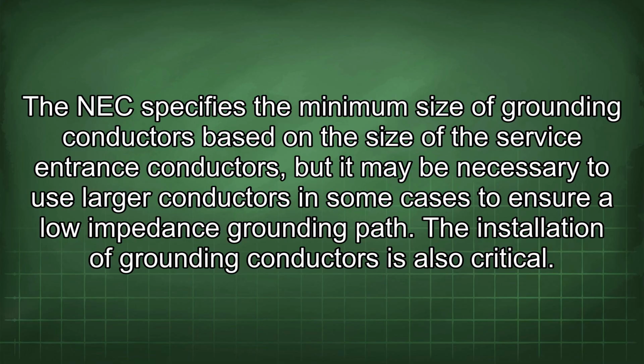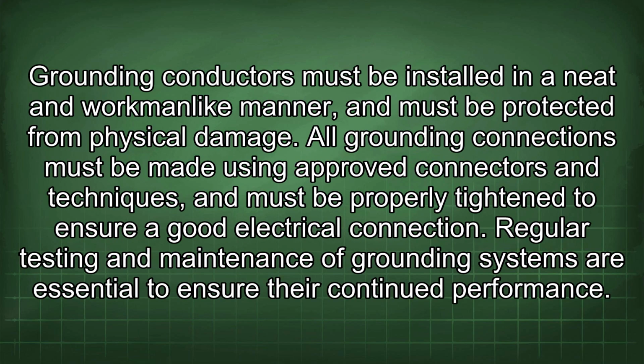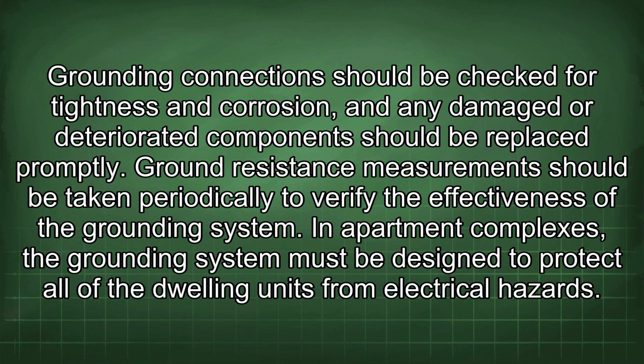The installation of grounding conductors is also critical. Grounding conductors must be installed in a neat and workmanlike manner and must be protected from physical damage. All grounding connections must be made using approved connectors and techniques, and must be properly tightened to ensure a good electrical connection. Regular testing and maintenance of grounding systems are essential to ensure their continued performance. Grounding connections should be checked for tightness and corrosion, and any damaged or deteriorated components should be replaced promptly. Ground resistance measurements should be taken periodically to verify the effectiveness of the grounding system.